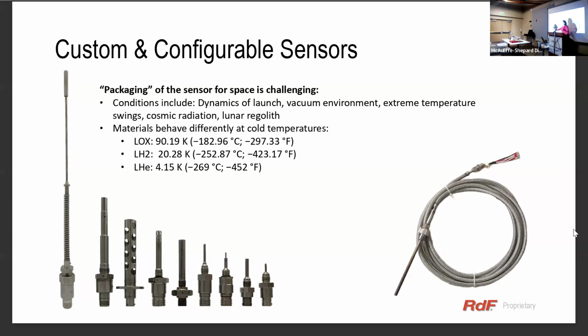You can see here a variety of probes, each with a different form function, optimized for the application it was installed in. Something like this little guy has a connector on the back end that lets you plug it in and pull it out easily. It has a standard small eighth-inch diameter probe tip, helping insert the RTD into a flow. There's threading around it which enables you to screw it into the pipe without a big leak.